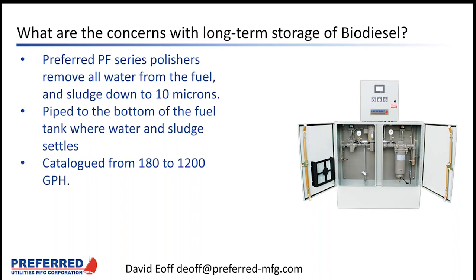The suction line for the polishers is piped to the bottom of the fuel tank where water and sludge settles. We recommend the suction line be on one side of the tank and the return line on the other side of the tank to help promote mixing in the tank. That way you don't get any dead spots in the tank where you'll have fuel that isn't getting polished. If your tank has a low end, like most tanks eventually do because they settle, locate the suction pipe at the lowest point in the tank.